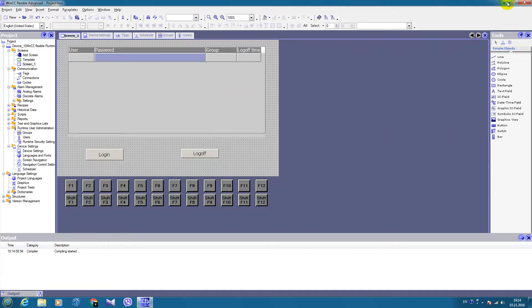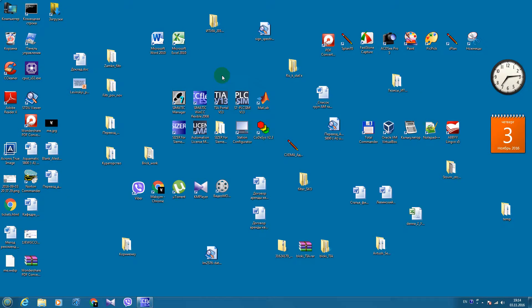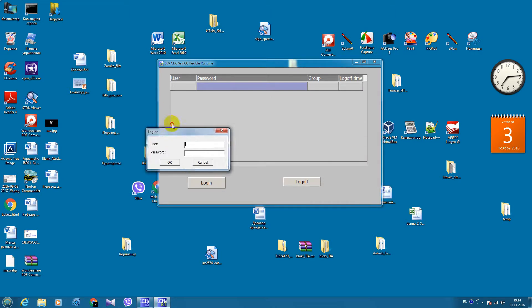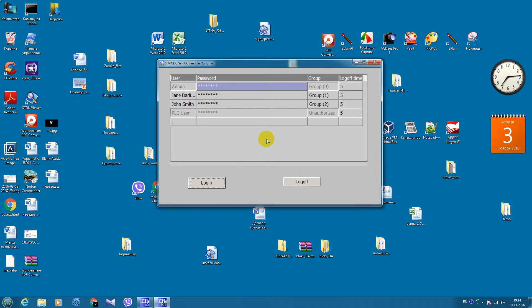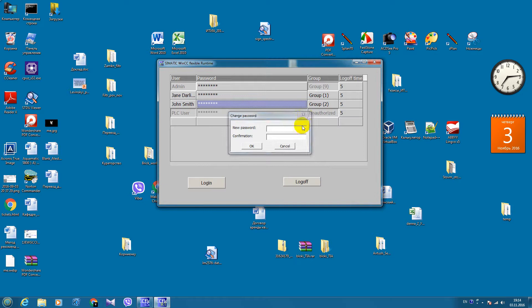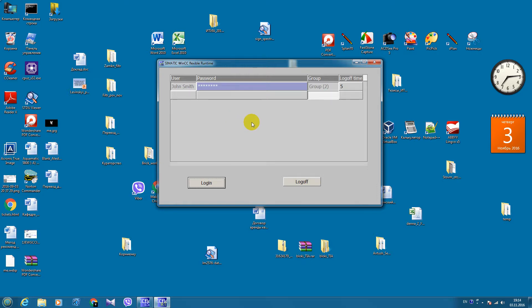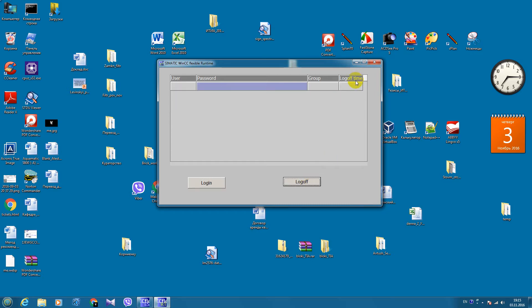Let's test it. As we login, we have this dialogue. Let's say it will be admin. Admin has all access to the project, as well as the ability to change passwords of other users. Let's log off and login as John Smith. We have logged on as John Smith, and in the project — if it is a big project — we have only the authorization for the technician, because John Smith is in the technician group. And we log off. That's how you can implement user administration in your WinCC projects.